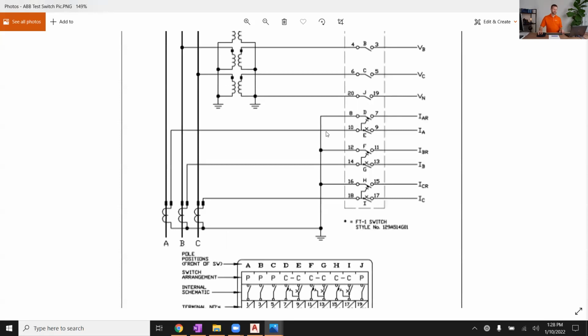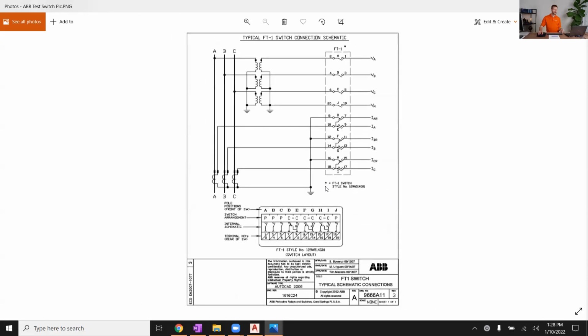And then notice that the neutrals are tied together or jumpered on the field side of your test switch rather than on the back of your relay. Otherwise, you wouldn't get 3 returns. You'd only get 1 common return, right? You've got to do that in order for this shorting test switch to work properly. Those are just a couple of things I'm pointing out to you on the concept of a test switch. We'll look at those a little more in some real life 3-line diagrams tomorrow.